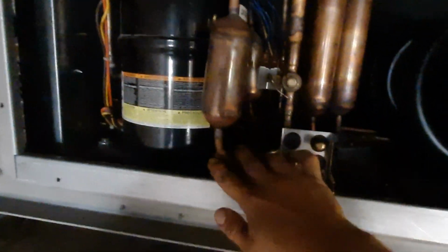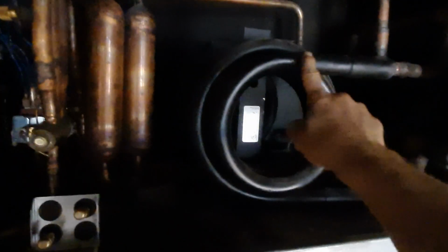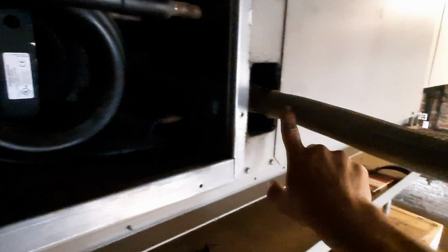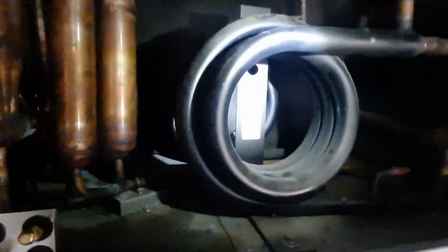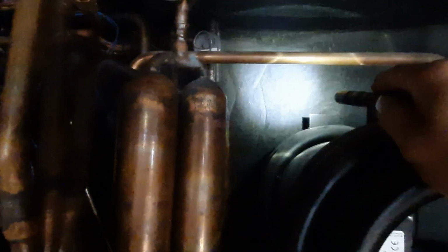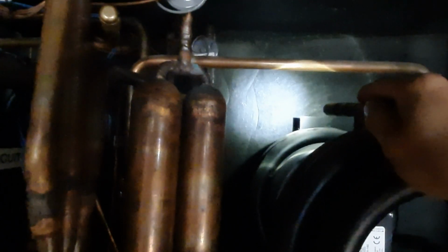It's a reversing valve, hot gas discharge comes out into our condenser coil. This is our coaxial condenser, so as the refrigerant flows through here, water flows through here as well. We have basically considered our circulating pump, consider that your condenser fan motor. It has to run to cool the refrigerant off. So flowing water through here, hot gas discharge goes through the condenser coil, condenses to a liquid, out as a liquid, hits our expansion device, in this case TXV, and feeds over to the evaporator coil behind that panel there. An evaporator coil does just what it says, evaporates that liquid refrigerant into a vapor, and we return back on our suction line to the compressor.